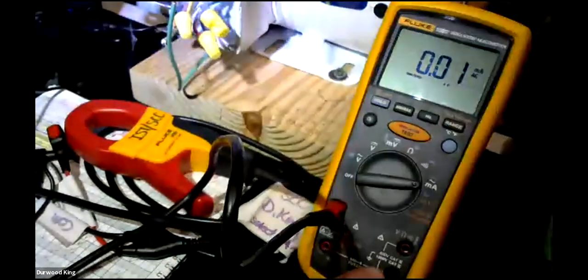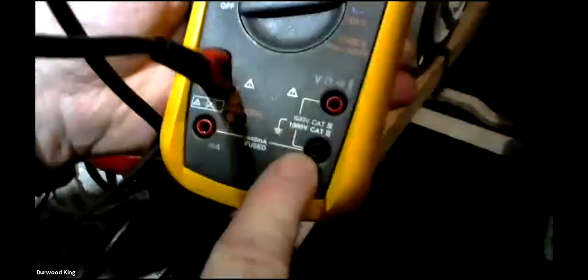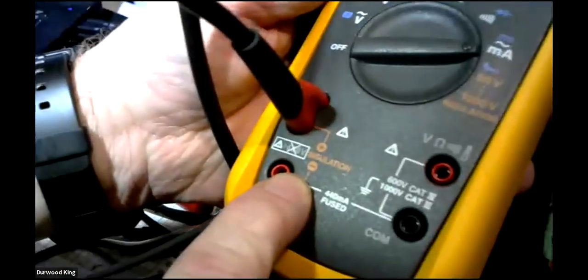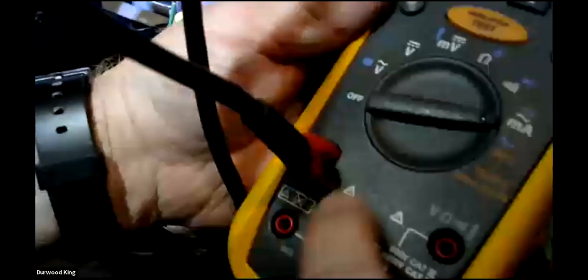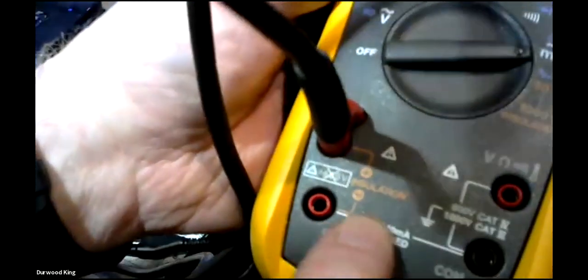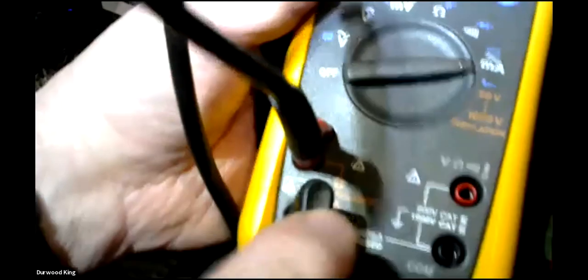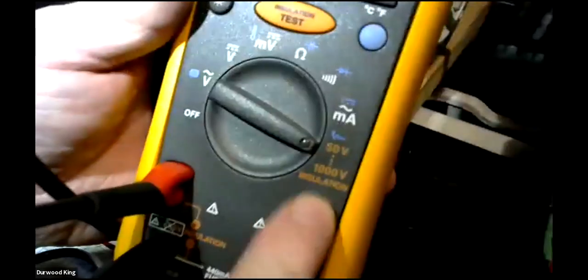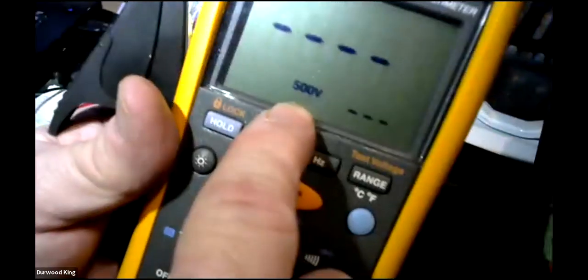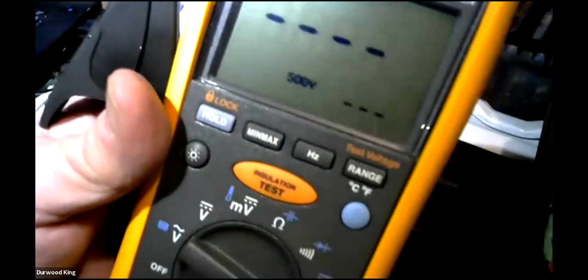Next thing, you put your common, you don't put it down here. You don't put it over here. You put it over here for minus on insulation. So if you're doing insulation, that's plus, and that's minus over there. You see that in orange? Yeah. So you have to go over here with your common to get an accurate test when you're doing insulation testing. You go to insulation, you choose your voltage, you're going to test that. Okay? And then you're ready.